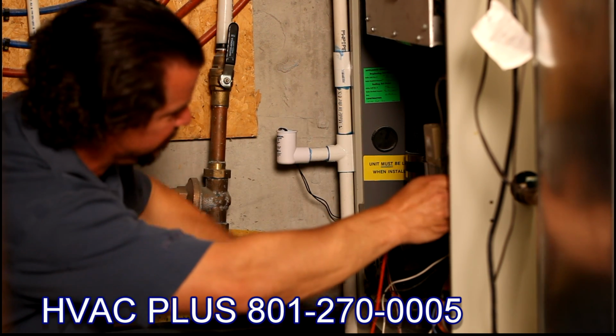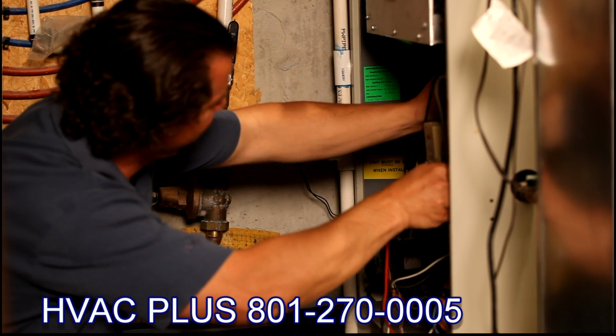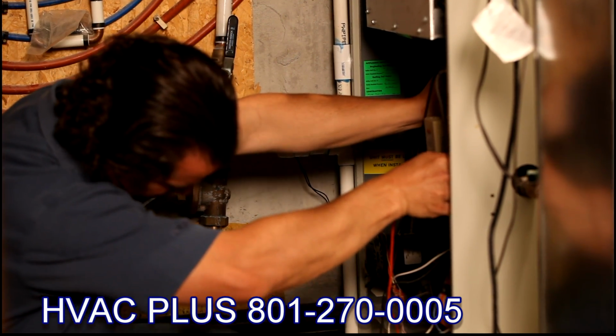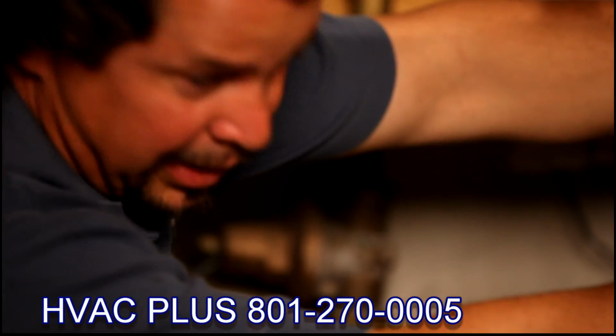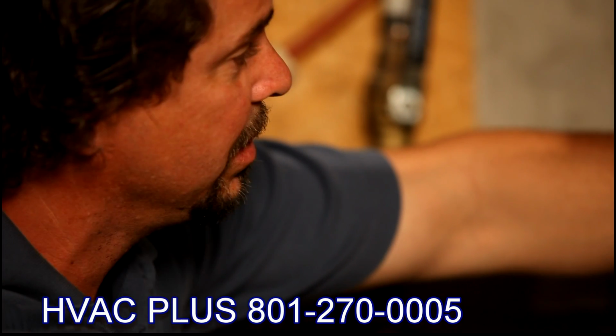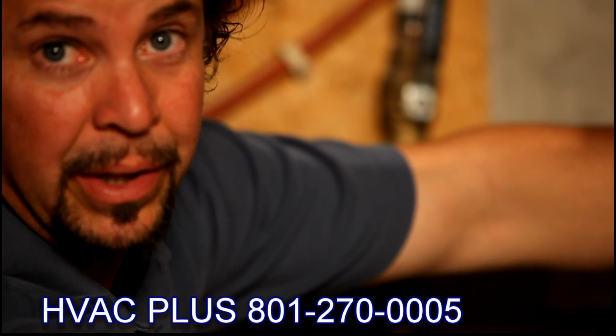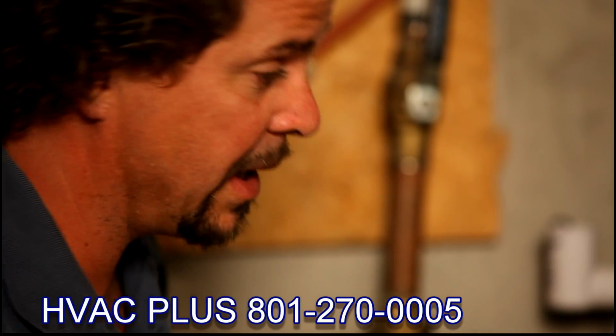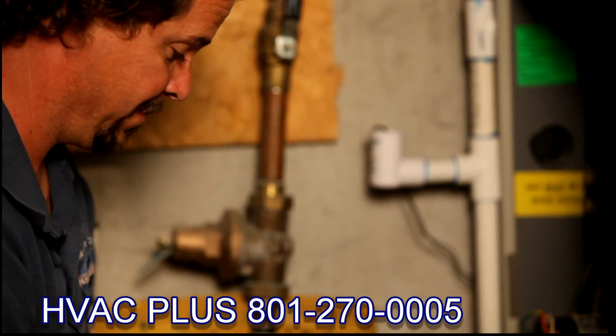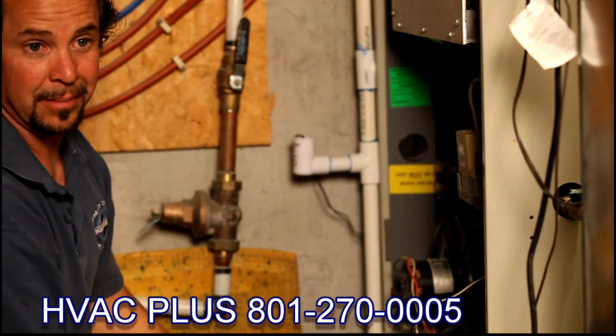Looks like you have an open fan limit, probably due to not changing your air filter. The most common problem with furnaces now is a bad, dirty air filter. So that's what we got here, just a bad, dirty air filter. Go ahead and change that.